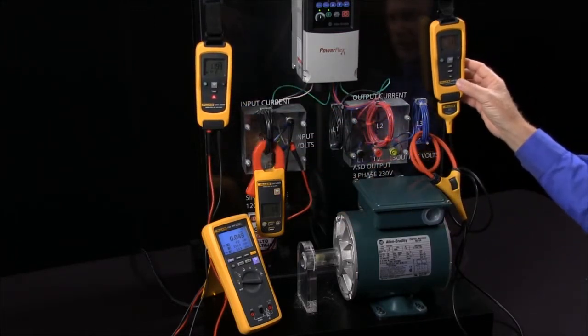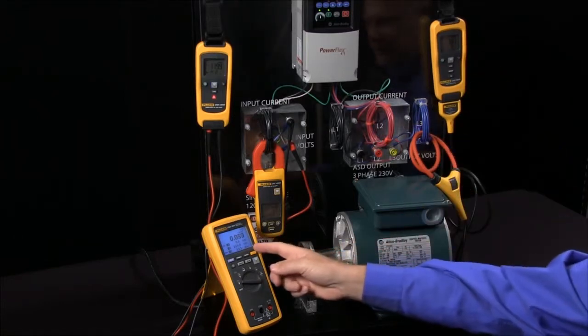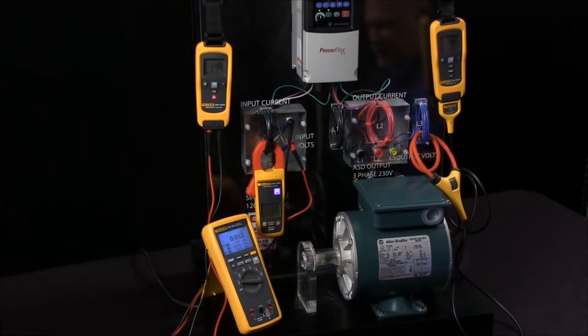And on the output over here, we have 13.1 amps using the flex clamp. So this is how we would configure the Fluke CNX 3000 to read data remotely from modules that are up to 60 feet away.